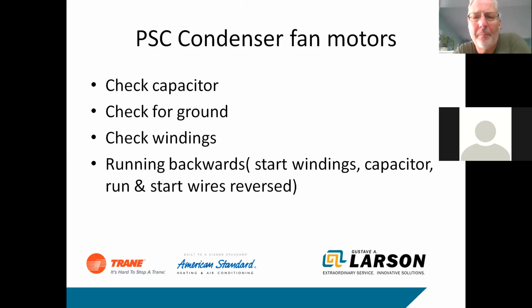And they've been around forever, but on those, you want to look at the capacitor. I think just about everybody has capacitor testers on their meters nowadays. The key thing with the capacitor, of course: turn the power off, disconnect the wires, make sure it's discharged. But check your capacitor out, make sure it's within plus or minus 10% of the value stated or listed on the capacitor. When we're looking at the motor, check for ground, check for the wires to ground. Check the windings, make sure we have some resistance on the windings.